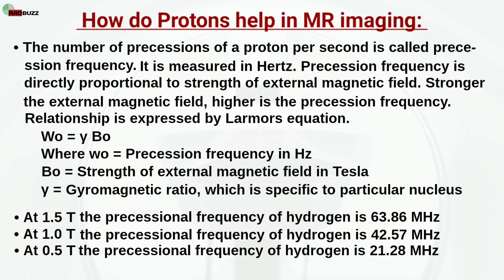Larmor's equation: W0 = γ · B0. Where W0 is the precession frequency in Hertz, B0 is the strength of the external magnetic field in Tesla, and gamma (γ) is the gyromagnetic ratio, which is specific to a particular nucleus. At 1.5 Tesla, the precessional frequency of hydrogen is 63.86 MHz. At 1.0 Tesla, it is 42.57 MHz. At 0.5 Tesla, the precessional frequency of hydrogen is 21.28 MHz.